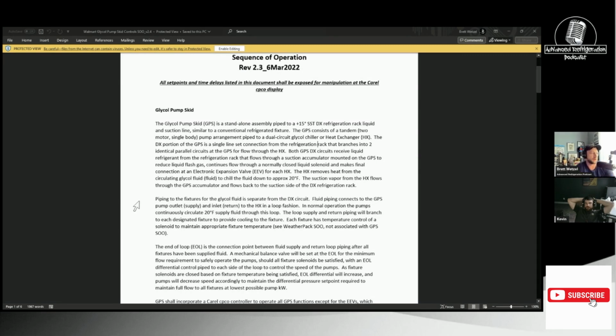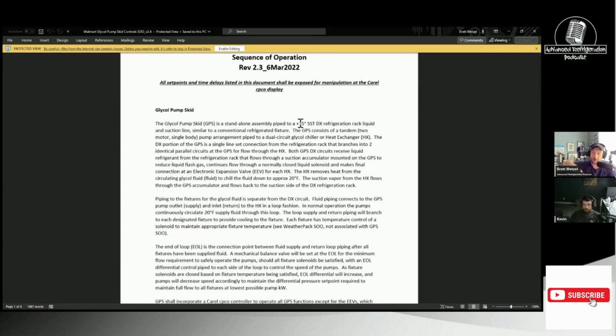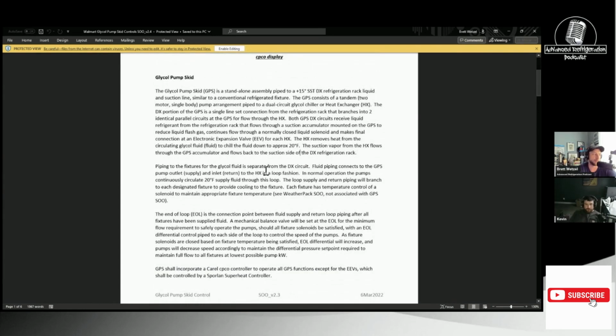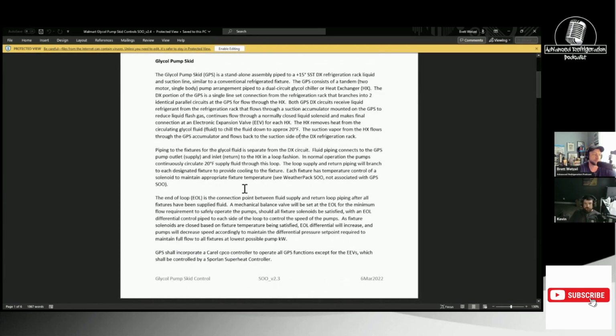So this is what I was getting at. This says right here, this would be with a very constant superheat, pipe to a plus 15. It depends on how far it is. I've seen some where the rack is down on the floor and the pump skid's up on the roof, and we'd have to drop the suction a little bit in order to maintain the 15-degree out of the actual pump skid. But it says with that, we should be able to run down to 20 degrees. I'm 15 feet away, so there should be no reason why it's not maintaining, right? It's literally 15 feet away.